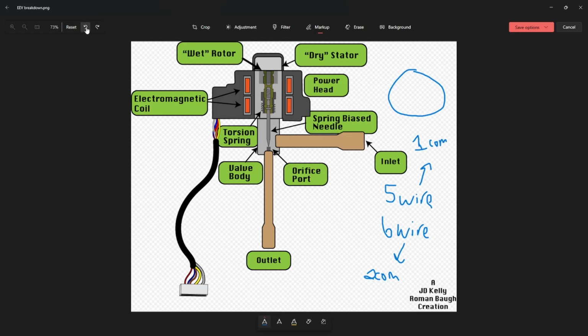On a regular motor, your stator is going to be in place, and your rotor is going to be what gets moved by the magnetic coils, because it'll have these poles around the motor that become electromagnetically charged with a positive or negative charge when they get voltage applied to them. That makes the magnetic field that actually creates motion of the motor itself. This has a dry stator and a wet rotor. Same thing. It's just a motor.